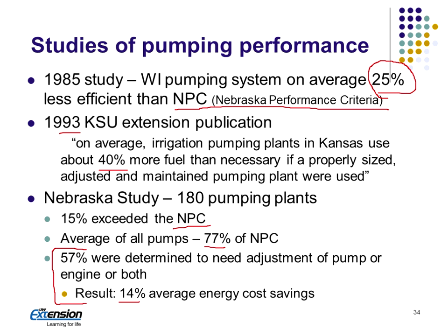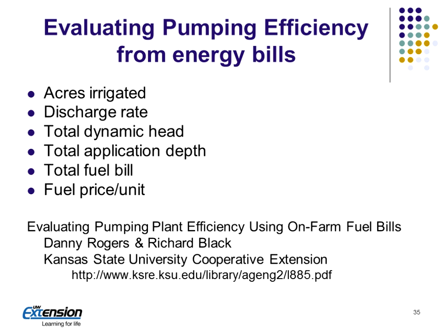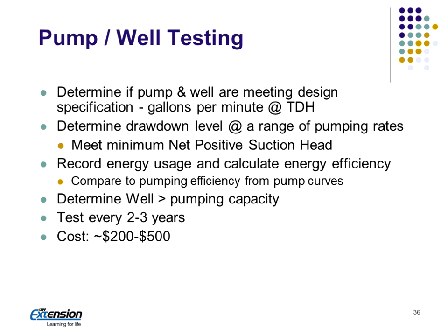So one of the things this pump test does is identify where you have a problem. Once you know the problem, you can determine whether it's economical to fix it and how to fix it. One of the ways we can look at our pumping efficiency is a publication that Kansas State did evaluating pumping plant efficiency using our energy bills. Basically here's the information you need, and if you go through that publication, you can estimate the efficiency of your system without actually having to complete the pumping test. At least it gives you a ballpark to see if you should spend the money for a pumping test, although it isn't very expensive.